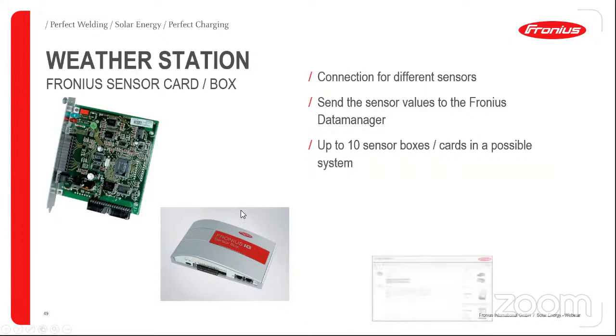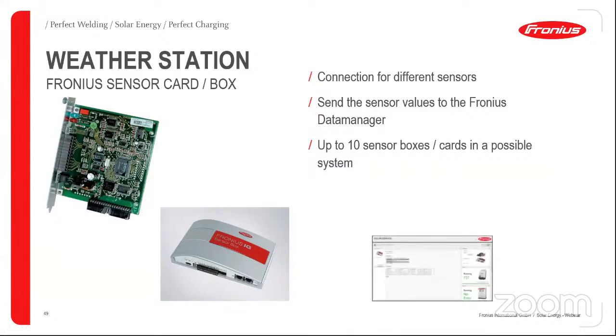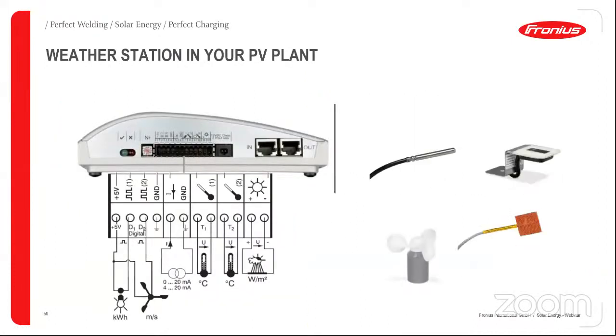The connection and all the commissioning for the weather station is exactly the same. You just keep in mind the distance between where you want to have the sensor and where the inverter is. So we have sensors for radiation, temperature in the module, and ambient temperature. We also have an additional point where you can connect speed of the wind, or also you can have a humidity sensor. This is up to connect whatever measure you need.